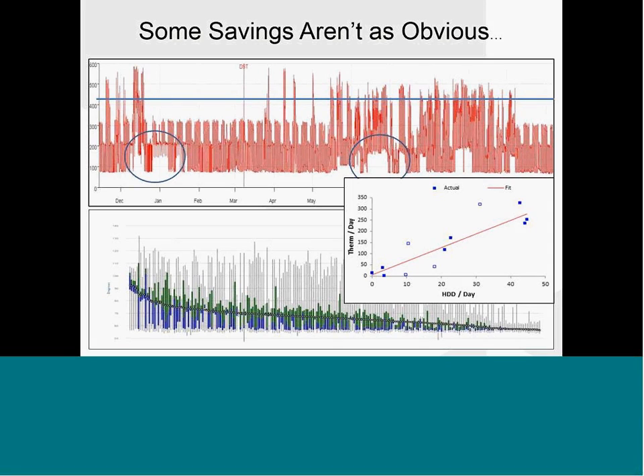We can take that information and compare it to the demand chart. Now, they're two different things—one's thermal, one's electric. But this told us about the building and gave us direction: this building is being overheated, and it's forcing chillers in another building to run more than they should. That's forcing some of our peaks, as well as maybe those evening periods where we saw those circles I noted. By combining that information together, it gave us direction as to where we might target. Keep these two charts in mind, because I'll talk back to them as I go into more example on this particular client—an example of where having newer, updated technologies to pull utility and building automation information together can really give you great direction.